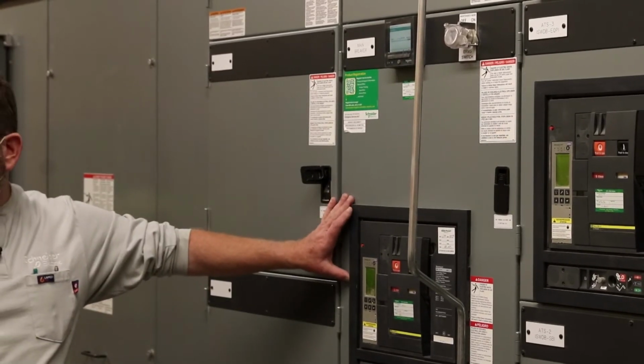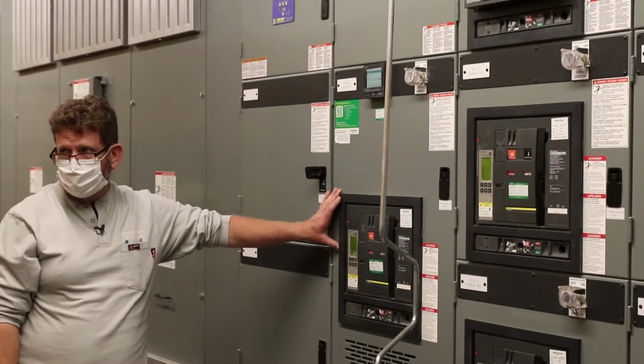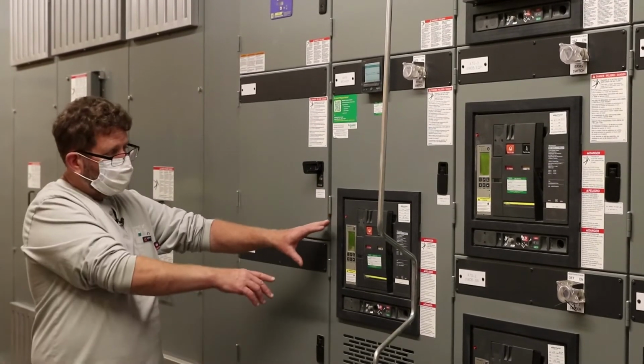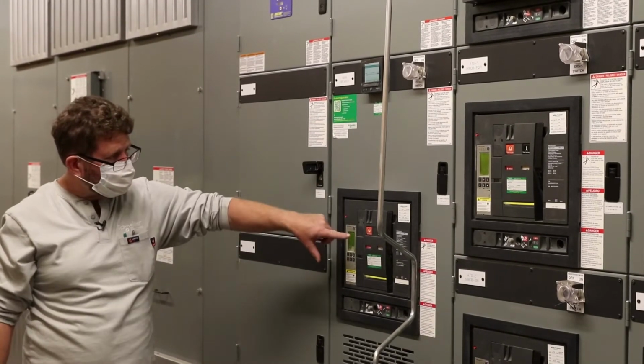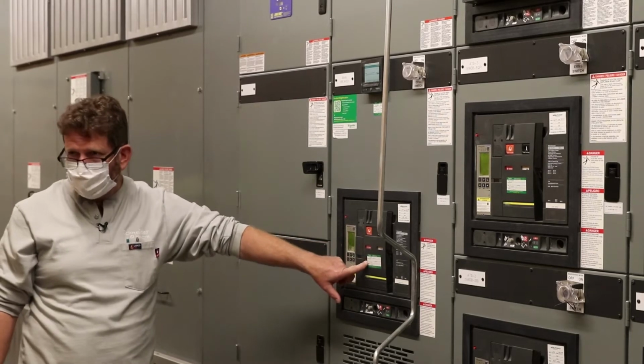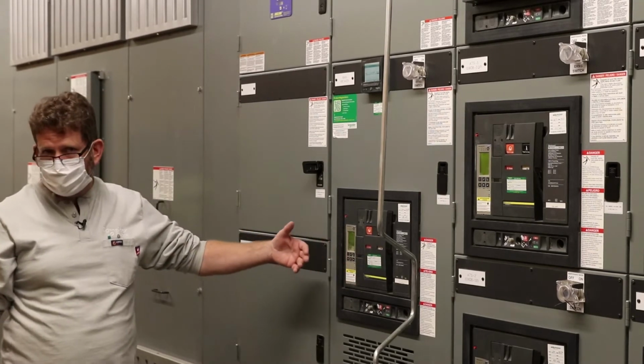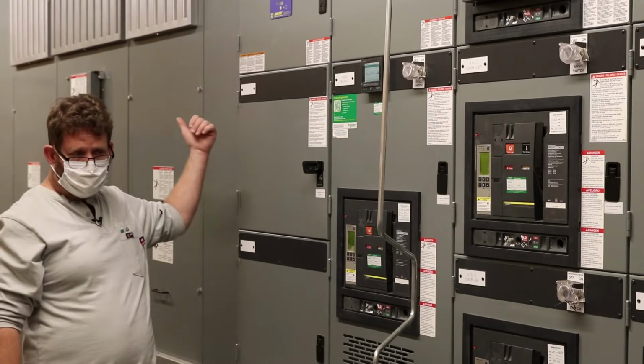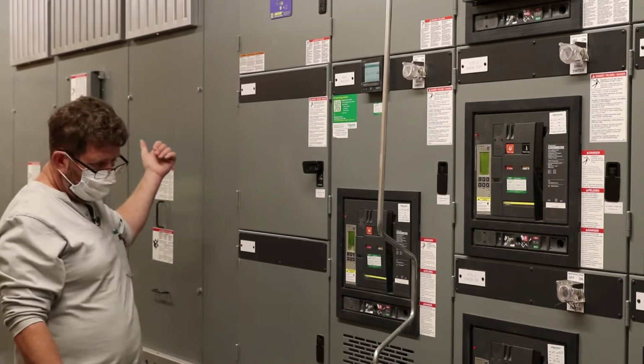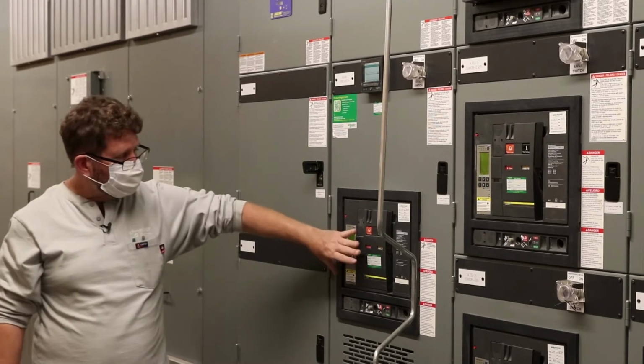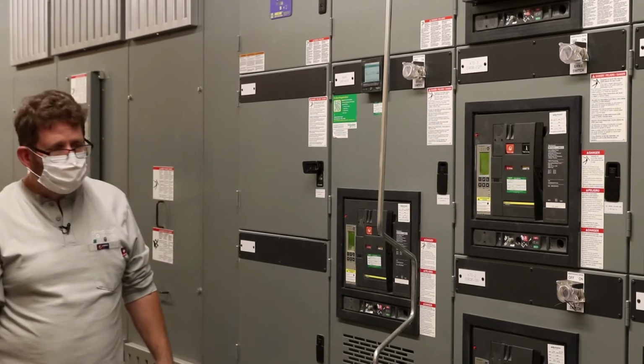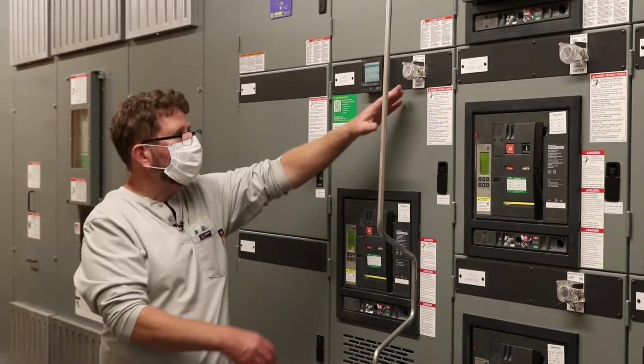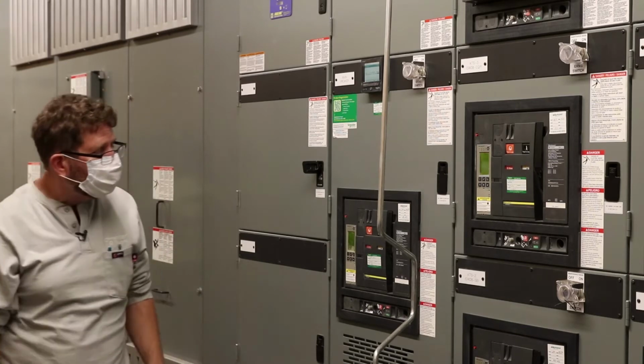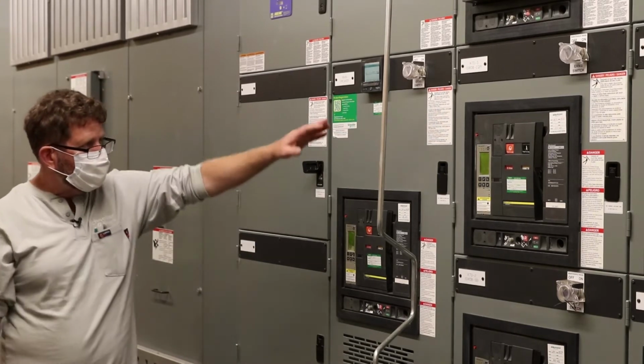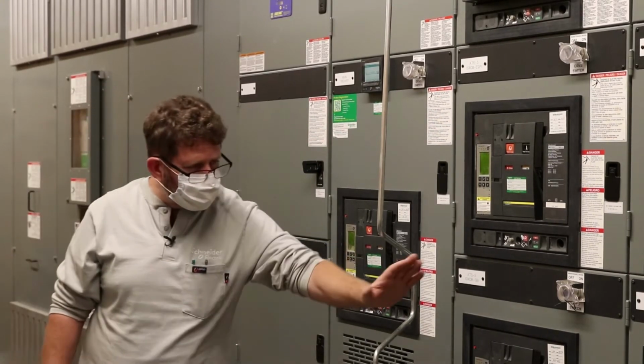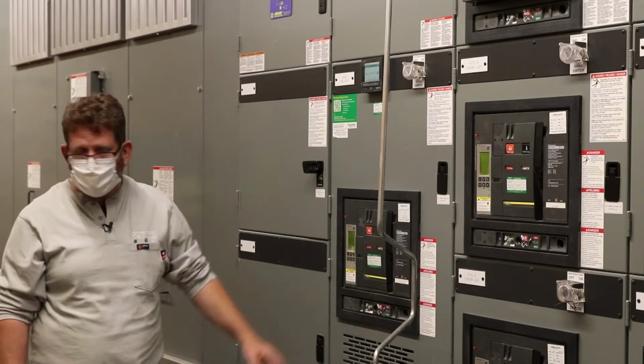It doesn't help you at all if you're racking the main breaker out, because all that's doing is making it so this will trip quicker. If you're racking this breaker out, this breaker isn't protecting you. You're protected by the line side or the transformer fuses. This breaker's already open. So it's kind of a common misconception that if you're racking this breaker out, you take the ERMS switch, you're doing something down here. The ERMS switch is only protecting you on anything downstream of what it's affecting.